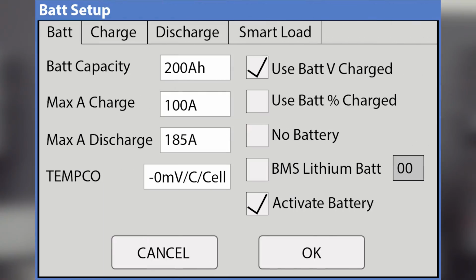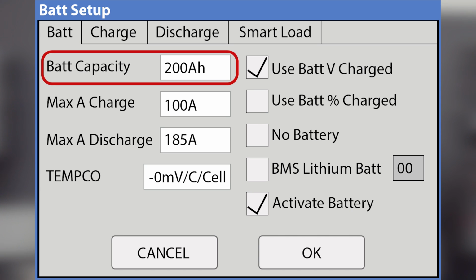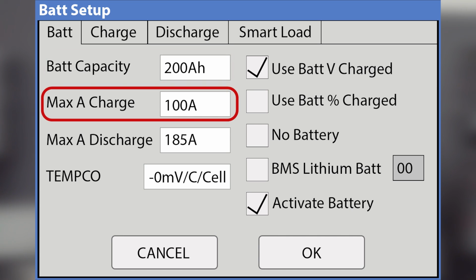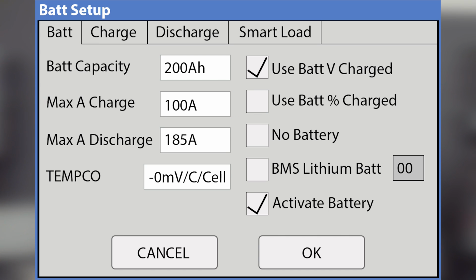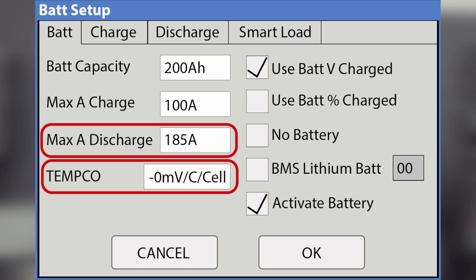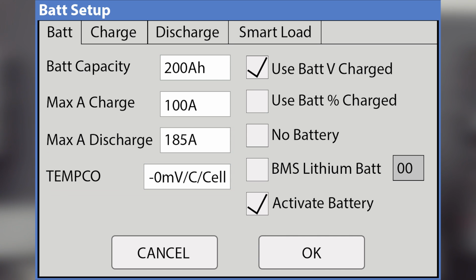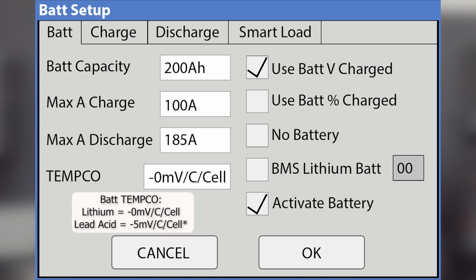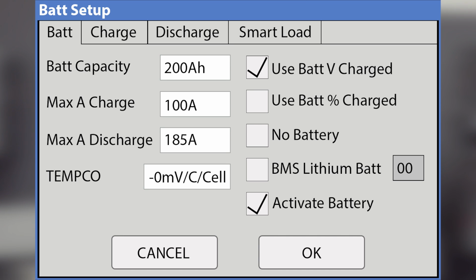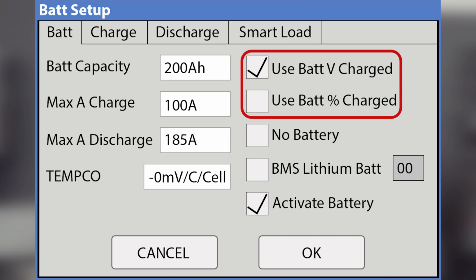If you do have a battery, you're going to want to set the capacity in amp hours. You just touch the box, you'll see a cursor, and then you can go up and down with the arrow keys here. You're going to go through your capacity, your maximum amps charge, or max A charge, discharge, and the temperature coefficient. The first three you should be able to get from the spec sheet from your battery company. Then your temperature coefficient, usually it's going to be 0 for lithium and about -5 for anything lead acid.